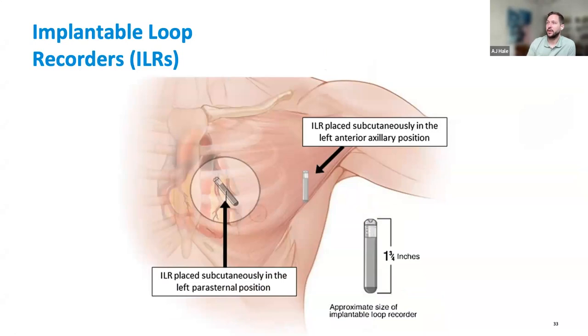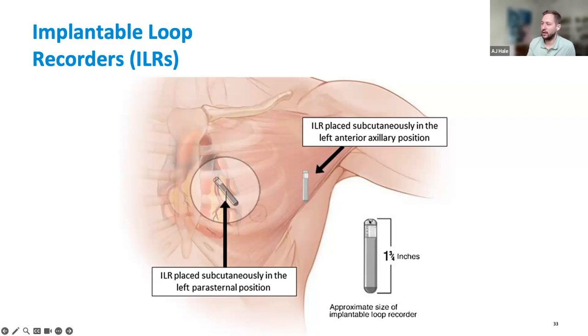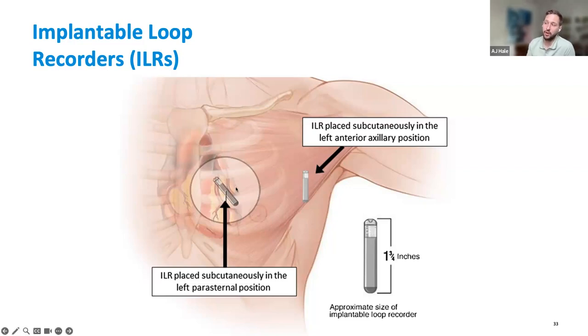Moving on, we have ILRs — implantable loop recorders. The idea is that it produces almost like a surface EKG. It's not inside the heart; it's just tucked underneath the skin, sitting above the heart. It has an electrode at each end and measures the electrical impulses across the heart. It's a good way to monitor for AFib and also to look for pauses. Unlike a Holter monitor which is short-term, the ILR has many years of life — most on the market are around three to five years. It monitors the patient continuously and saves EGMs that can be reviewed and associated back with symptoms.